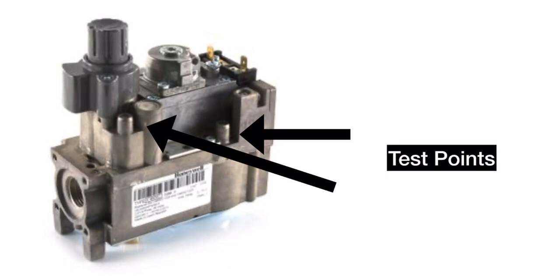It should be reasonably easy for you to navigate your way through carrying out any of the tests. You can only carry out two tests on this, or three tests, in fact. You've got the two pressure tests and testing the FSD. You can switch it on and off at the wall and check whether the solenoid is operating. But really, all you'll be required to do is to light and check inlet pressure and burner pressure.